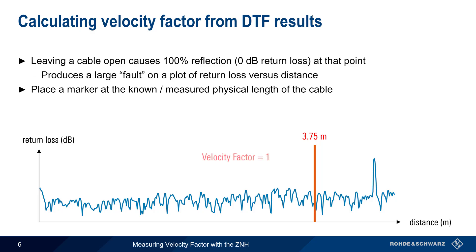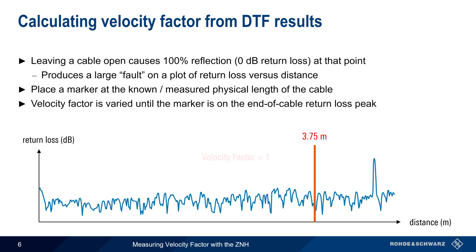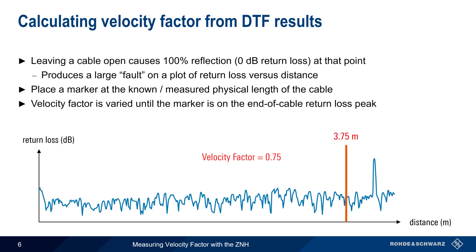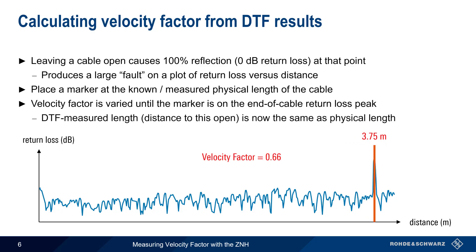If we start with a velocity factor of 1, this marker will always be to the left of our end-of-cable fault. We then adjust the velocity factor until the marker is on the end-of-cable return loss peak. At this point, the length measured by the distance-to-fault measurement and the physical length of the cable will be the same, indicating that we are using the correct velocity factor for the cable under test.